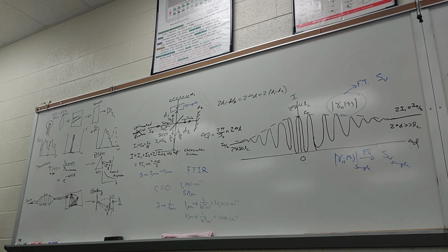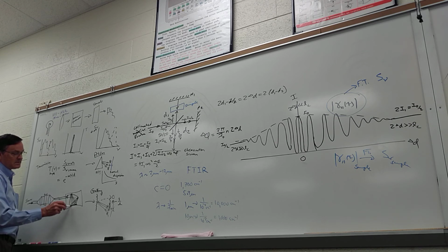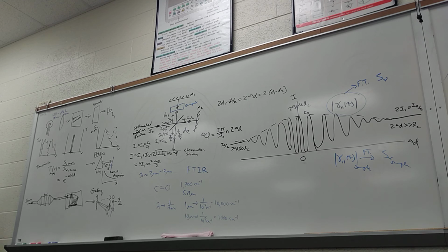The reason is that we wanted really low noise, so we paid for it. Low noise means this silicon linear detector array is put on a thermoelectric cooler that uses the Peltier effect to reduce the temperature of the silicon, and that reduces your noise. So that works pretty good.